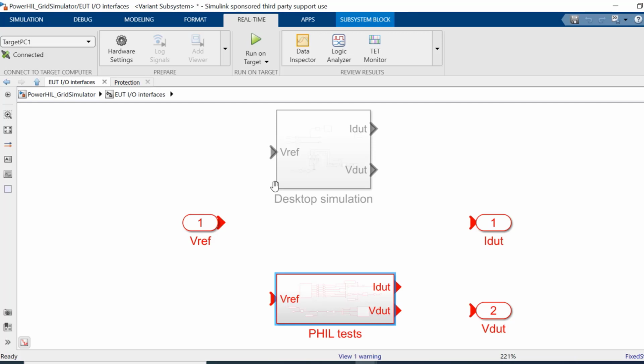It is good practice to test your interface algorithm, connecting to the rest of the system with the equipment under test, in desktop simulation prior to power hardware-in-the-loop testing. For that reason, we use variant models to switch between desktop simulation and power hardware-in-the-loop testing. In the desktop simulation, we have a representation of the equipment under test. For power hardware-in-the-loop, we just need analog input and output interfaces to the power amplifier.